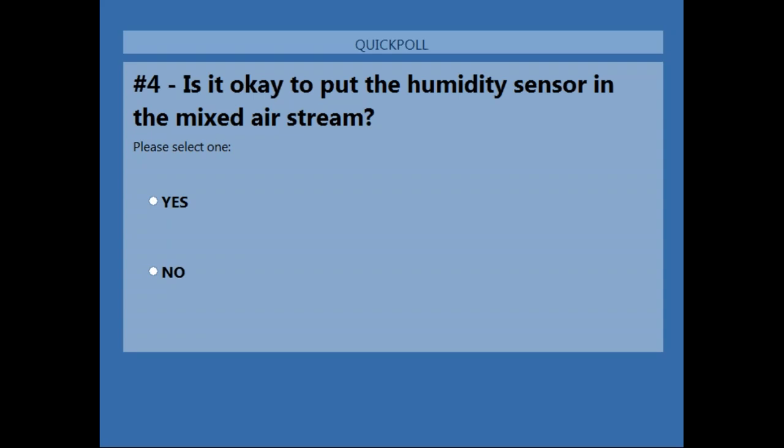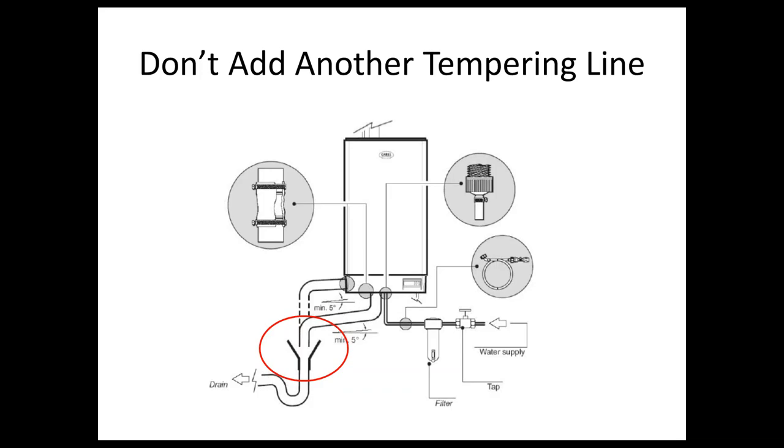Clarification on quiz question three: several people noted that if using a hose there are no elbows, so answers A — 20 feet — and B — 20 equivalent feet — are both correct. When using rubber hose, you want gradual bends rather than tight 90s. It is always 20 equivalent feet as the limit. For the PDH answer key, both A and B will be accepted as correct. Quiz question four: Is it okay to put the sensor in the mixed air stream? 79% answered no — correct.